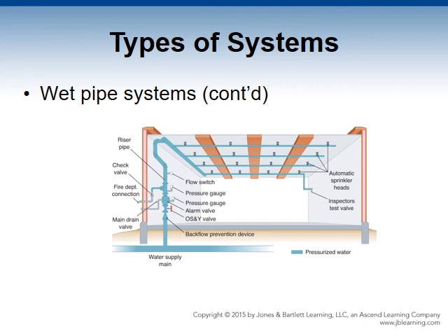They may be mechanical with a water motor, gong, or electrical with a retard chamber and pressure switch tied to an electric bell, fire alarm, or monitoring panels.